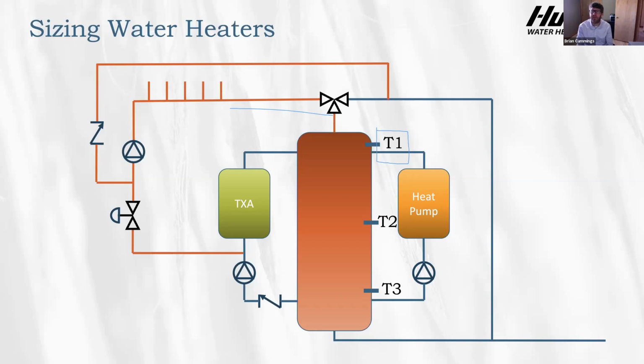If you had a very large boiler room and a very small heat pump, could we do it? Yeah, we could look at doing that. But the boiler room is generally going to be conditioned as well. So the heater will come on if we drop the temperature in there too low, and we don't really want to do that. So there's also codes. I know in California you cannot do that, but I'm not sure about other places, to be honest with you. But most of the time it's going to require the heat pump is pulling in outdoor air or otherwise unconditioned air just because of the amount of cooling that they provide. Yeah.